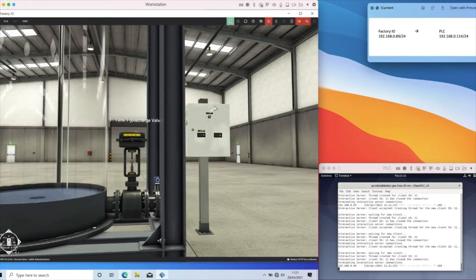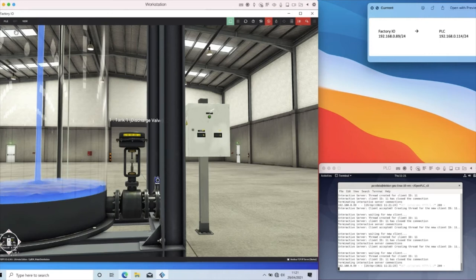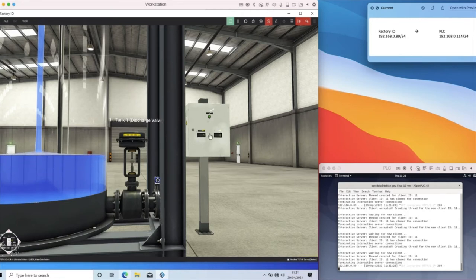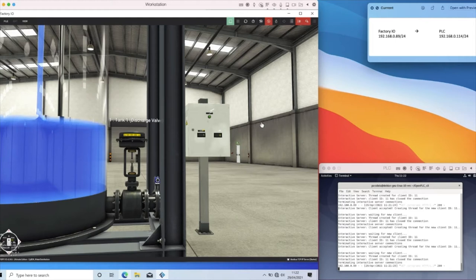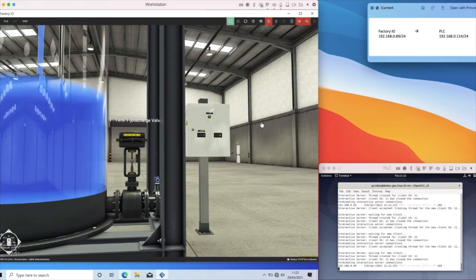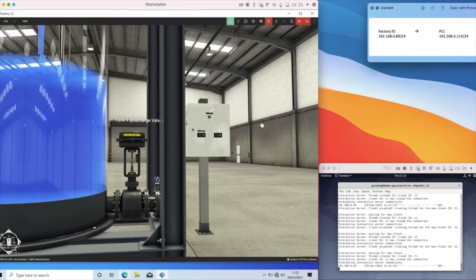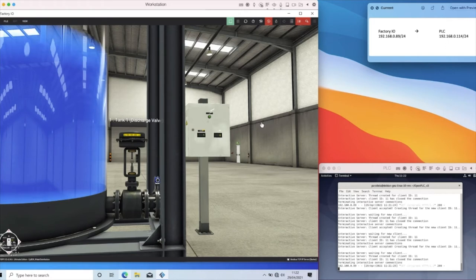We can control the PLC and the sensors from factory IO. We've got a fill sensor, a discharge sensor, a start button, and some registers where we're measuring and storing values. This is great when you're on the factory floor — you can see and control what's happening on the plant. But what happens if you're in a remote location? Water distribution plants are typically remote and require management but won't necessarily be manned. So we're using something called SCADA — Supervisory Control Data Acquisition — to observe what's happening from a remote location. During this video, I'll show how to set up and install SCADA BR, which is another part of the Open PLC project.